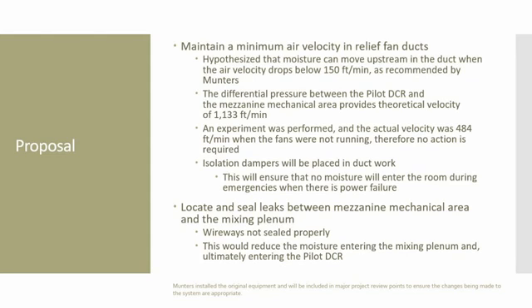The final proposed idea that we had was to seal all the leaks between the mezzanine and the plenum. There are many wireways that were not sealed properly. By properly sealing the mezzanine, it will reduce the chance of moisture entering into the mixing plenum and ultimately into the dry clean room.